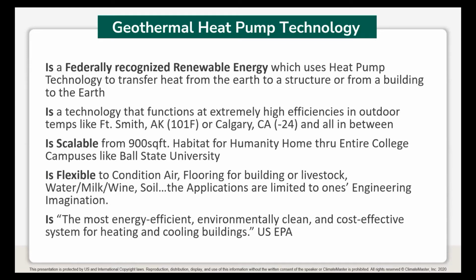Geothermal heat pump technology is recognized by the federal government as a renewable energy. Its purpose is to transfer heat from the earth to a building, or from a home building to the earth. It doesn't make heat, it just transfers heat. It's a technology that functions at very high efficiencies, regardless of outdoor temperatures. We rely on stable ground temperatures. So the fact that we have a design temp of over 100 degrees in some areas of the country, or a design outdoor temperature in the -20s, doesn't affect geothermal heat pumps with regards to their efficiencies.